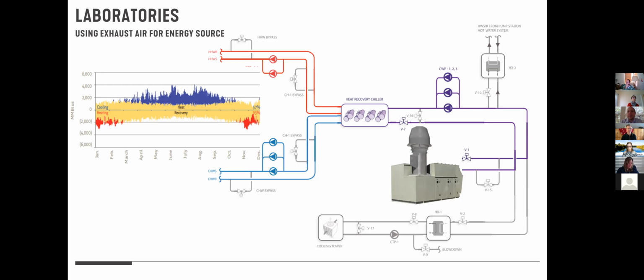Now, the nice thing about a heat recovery heat pump chiller or heat recovery heat pump, especially in the 6-pipe version, is that we also can go and grab excess energy from another source if we need it. If those two things aren't balanced perfectly, we can go somewhere else to grab that energy or to dump energy as we need to. In the case of a lab, a great place to grab energy from and push energy to is actually the exhaust airstream.